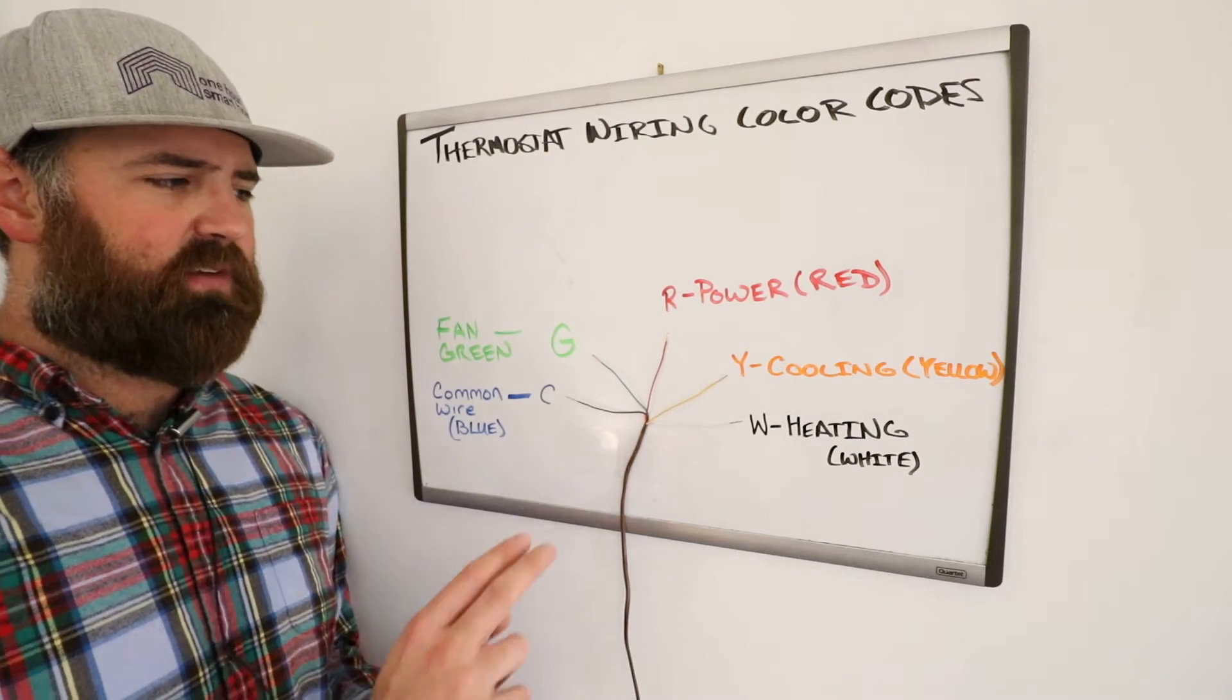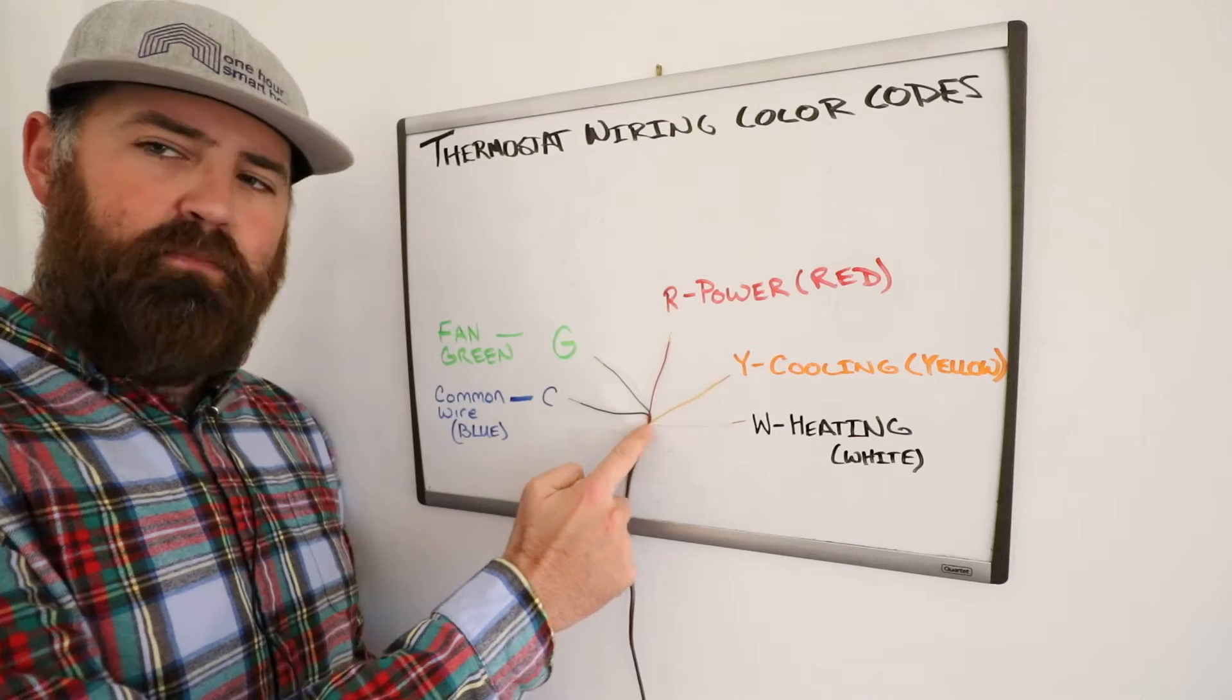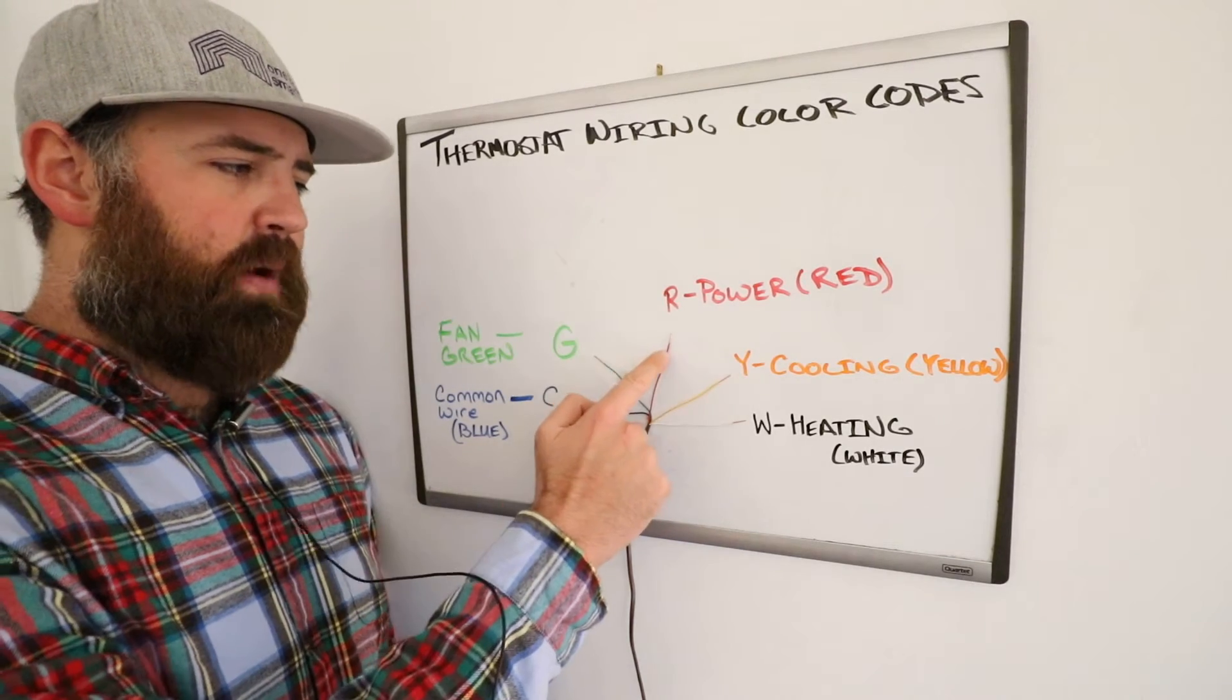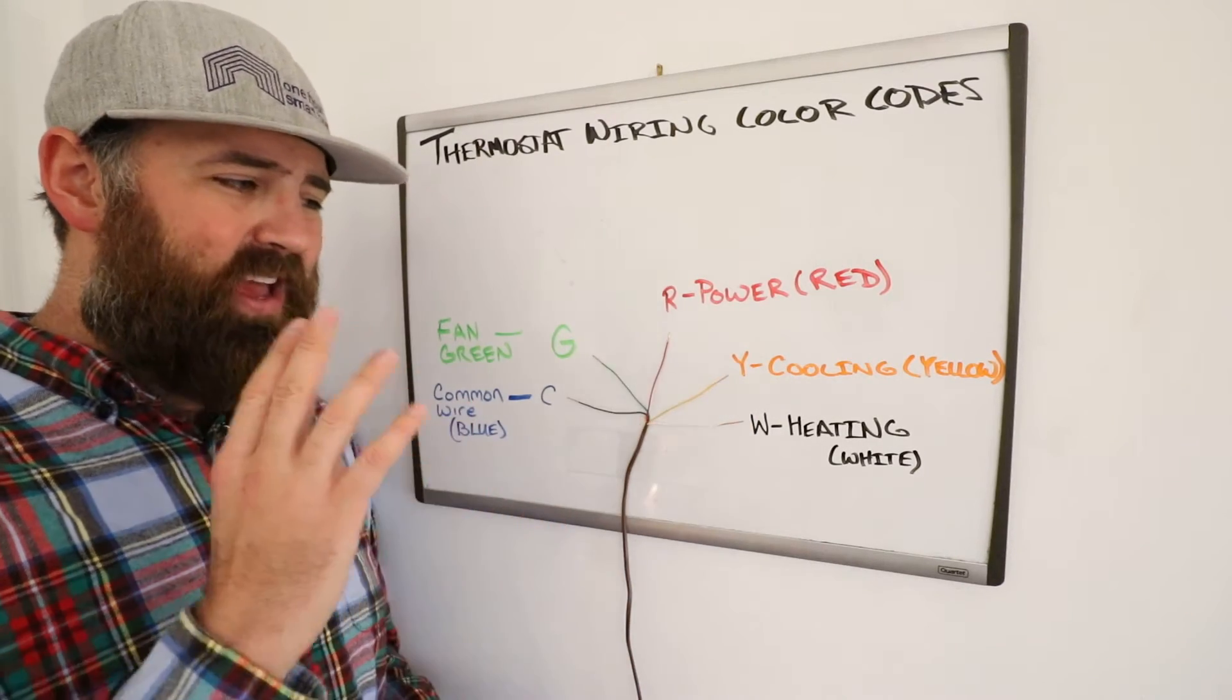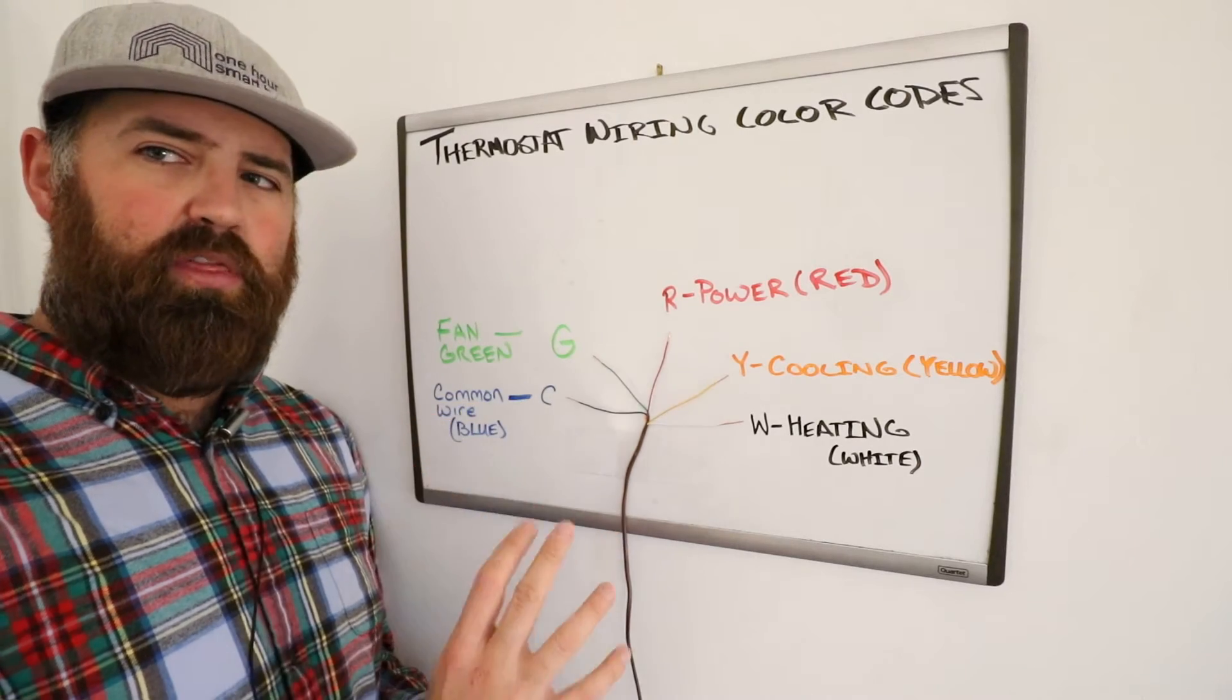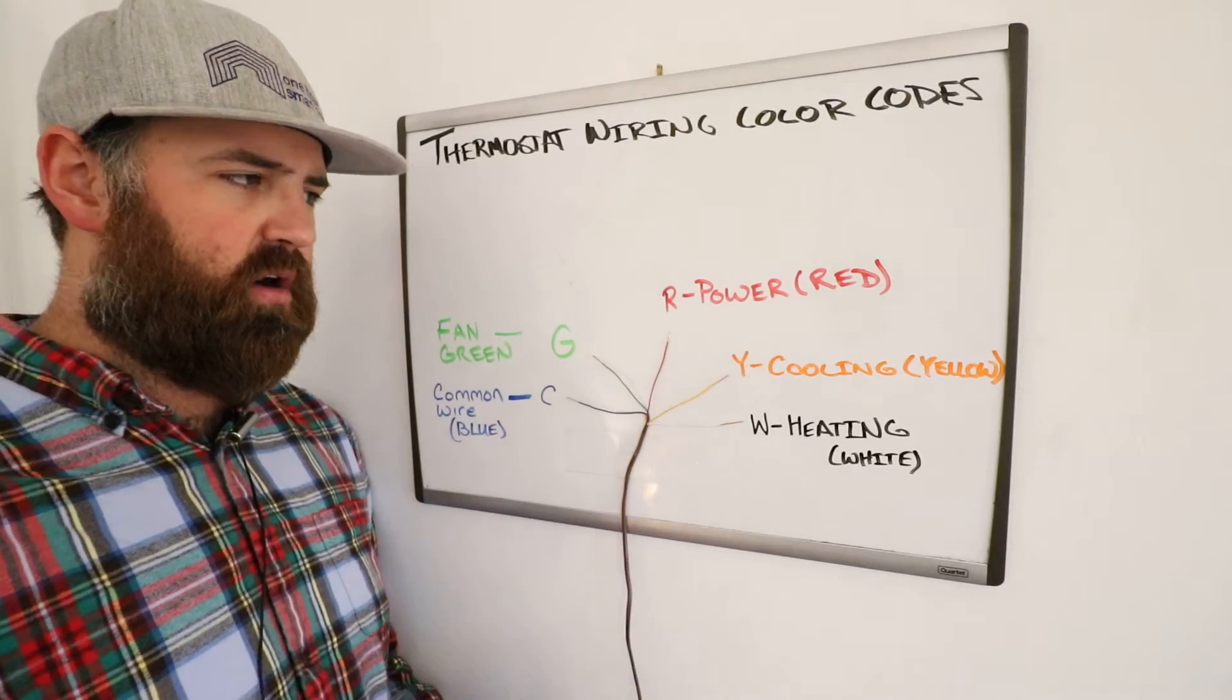And what happens when your thermostat activates any one of these other wires is that the power from this R-wire goes down, let's just say the Y-wire, and then back to your furnace, and that tells your furnace to turn on cooling, which is what the Y-wire means. Or if you had heating, the power from the R-wire would go down to the heat wire, and it would go back to your furnace or HVAC system and tell it to turn on the heating. So the R-wire is the most important, and it is the only one that will have power on it until your thermostat has turned on or detected another mode of too hot or too cold and told your HVAC system to turn on or off.